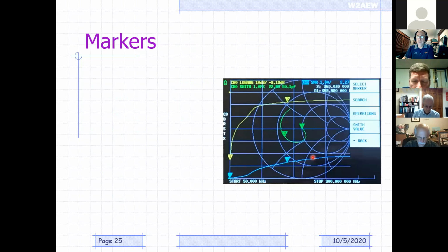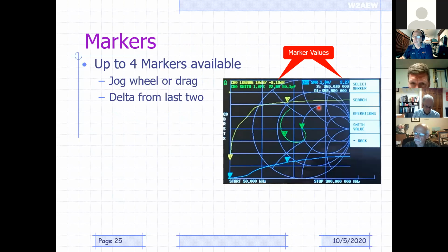Okay. And then there's markers. You have up to 4 markers available on any of the VNA firmware that I've seen. And so if you look at the display, this is kind of a typical display here. I can see the yellow trace is channel 0 showing log magnitude. Since it's channel 0, it's log magnitude of S11. And the 10 dB slash means it's 10 dB per division. And the value following that is the value of where the active marker is. Okay, the active marker is shown right down here. In this case, the active marker is 2. So if I look at marker number 2, it's sitting at 360 megahertz, and its value on channel 0 is minus 8.19 dB. Okay, so the selected marker again is shown there.